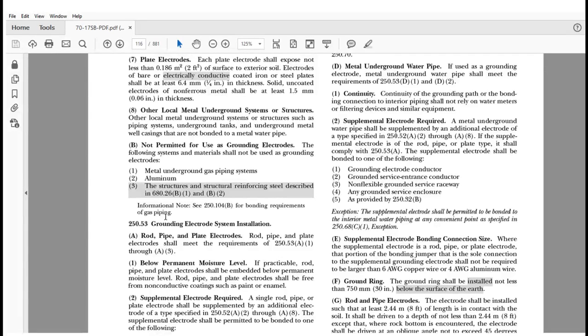Again, the equipotential bonding requirements of 680.26 are to reduce voltage gradients. The key is to reduce the differences of voltage between two conductive objects, the difference of voltage potential. That's what we're trying to deal with when we're doing equipotential bonding. It has nothing to do with creating a grounding electrode system for a building or structure. Okay, so that's what takes place here. Another important aspect to understand is that 680.26(B)(1) and (B)(2) are specific to Article 680, which can change, augment and supplement chapters 1 through 4.